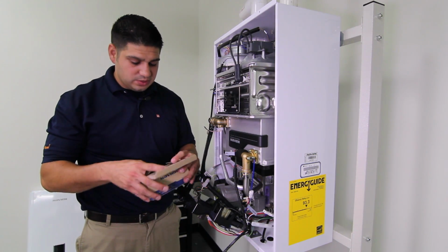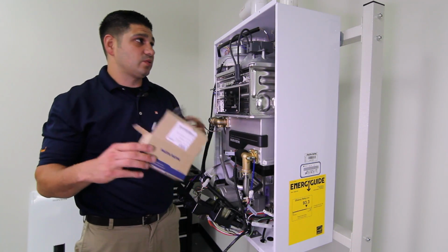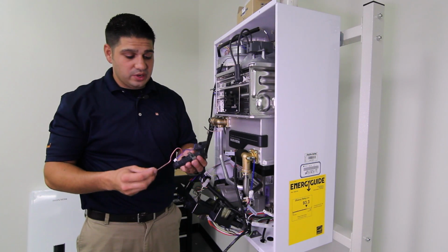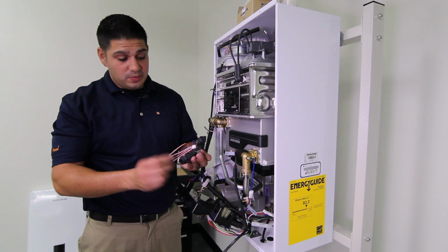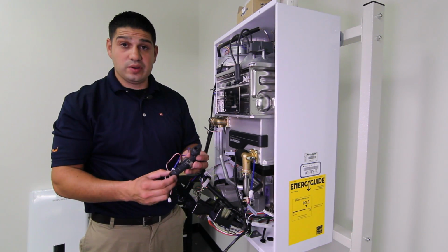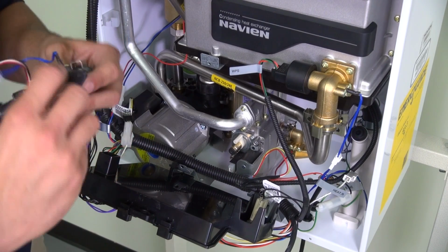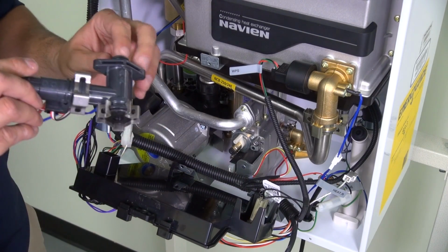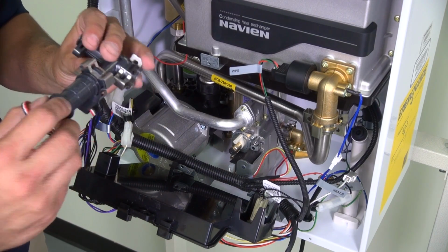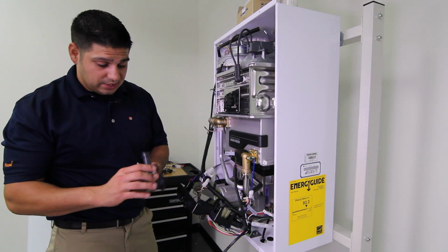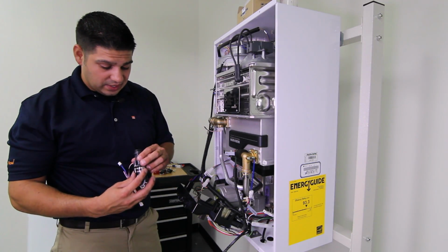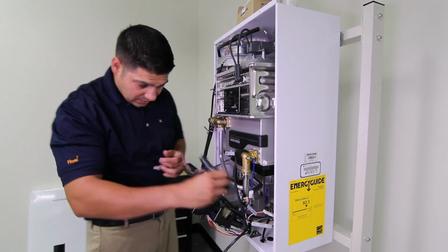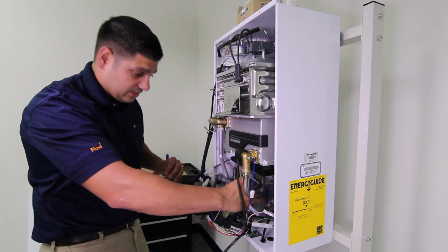Now I'm going to do a physical inspection on this flow sensor to make sure there's no shipping damage. The O-rings are already provided for you, so just do a physical inspection on them, making sure there's no leaks, cracks, tears, pinches, or anything of that nature. Looks like we got a good flow sensor here, everything's working fine, so let's start reinstalling it.